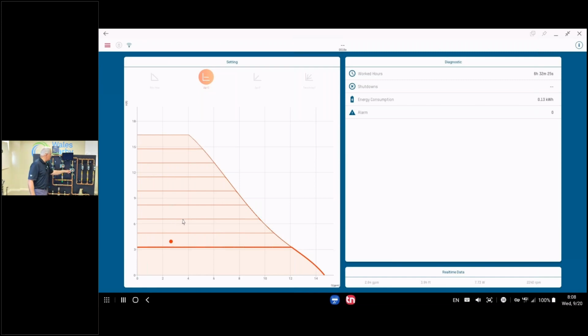The other cool thing about this circulator, I have the different modes. So on the box, we do explain what the different modes are. I'll get a little closer so you can see it. Okay, the blue mode is if I'm going to be doing a fixed speed. So if I want a dedicated fixed speed, I can do that. The orange mode is the constant pressure mode, that would be what we would recommend for zone valves. The green mode would be what we would recommend if we're doing a constant circulation system, that would be with TRVs, or what we know as the Danfoss valves. Those are non-electric zone valves. Those zone valves will open and close based on air temperature, but they're not connected to anything. And there is a bypass under them so we can have constant circulation. It's more the European method of doing things.